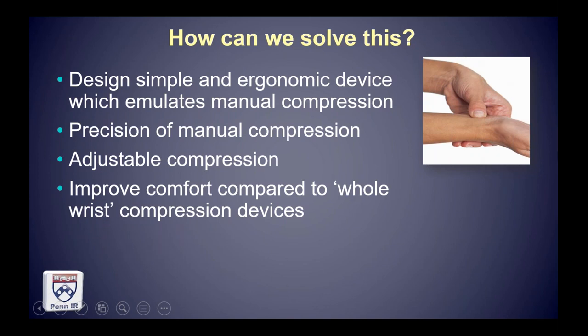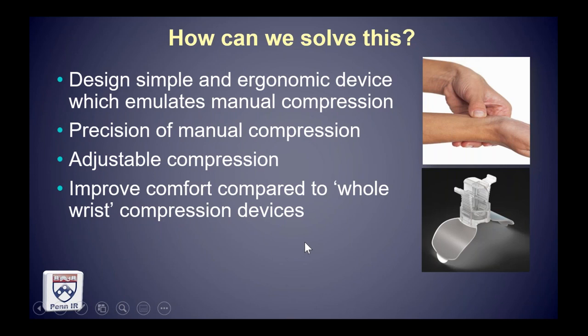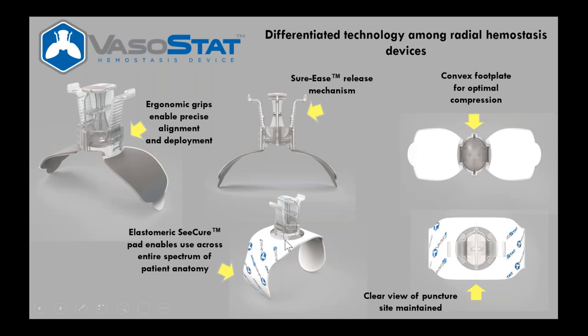So if you take the physics of manual compression and turn it into an ergonomic simple device that's very intuitive to use — that was the rationale, and that led to the VasoStat device. It has a ratcheting plunger, which is basically the thumb, and adhesion to the wrist accomplished through adhesive footplates and an elastomeric pad that goes on top — that's your fingers. You take your thumb, you align it and adjust it, and the rest of the device follows.